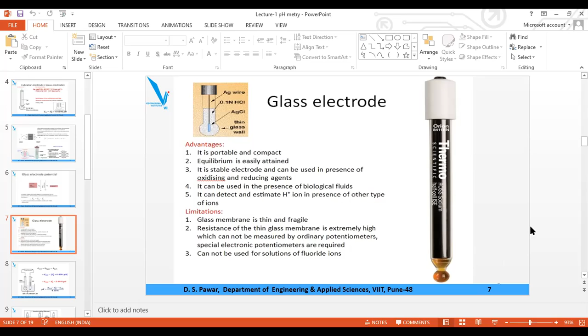Only the problem is that it is easy to break, fragile, and therefore utmost care needs to be taken. If it breaks, the whole solution will come out, and then you have to replace it with another one. The cost of this is minimum 2 to 3,000 depending on the manufacturing company. So these are the advantages and disadvantages of the glass electrode.